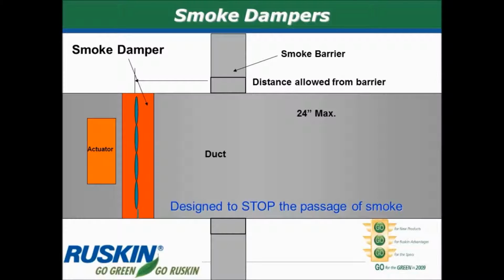A smoke damper designed to block the passage of smoke through a rated partition can be installed within 24 inches of that partition. This is a little different than what we see with fire dampers. Fire dampers usually need to be installed right in the plane of the wall or ceiling or floor that they are protecting. However, with smoke dampers, they can be installed up to 24 inches away and still be valid, still be completely proper. The big thing is, though, there can be nothing in the duct or connected to the duct between the damper and the wall. In other words, no branch takeoffs in that space between the damper and the wall, no access doors, no registers or diffusers. So it has to just be a solid, straight, unbroken piece of ductwork between the damper and the wall.